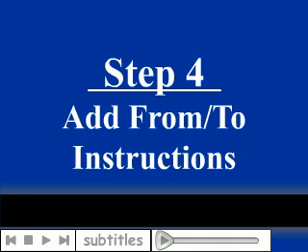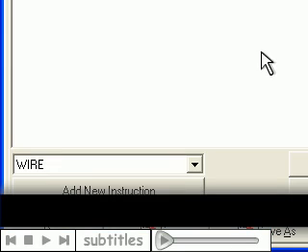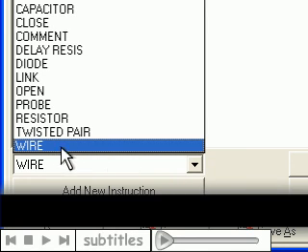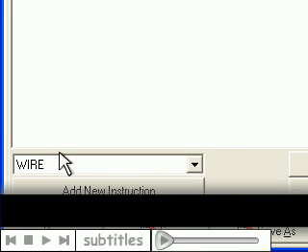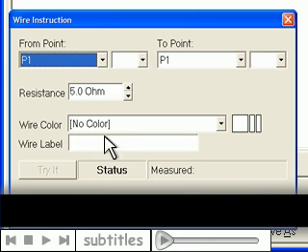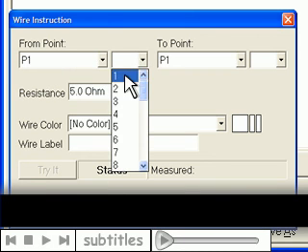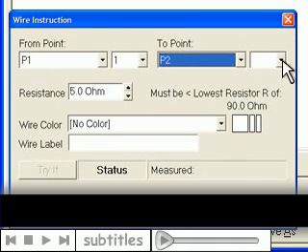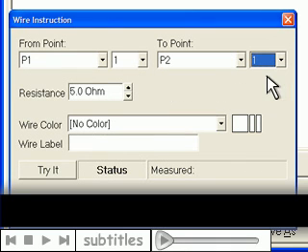Finally, you input the test instructions or from-to wire list information. From the drop-down menu, select the type of from-to instruction you want, then click the add new instruction button. Select the from point connector and pin, then the to point connector and pin.